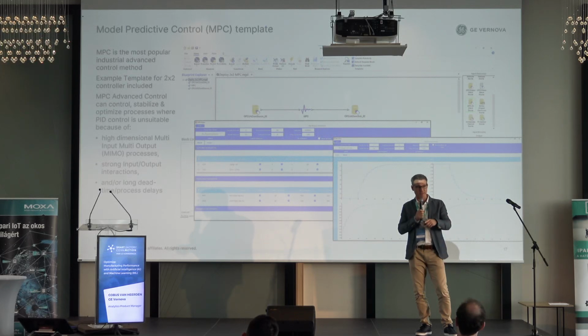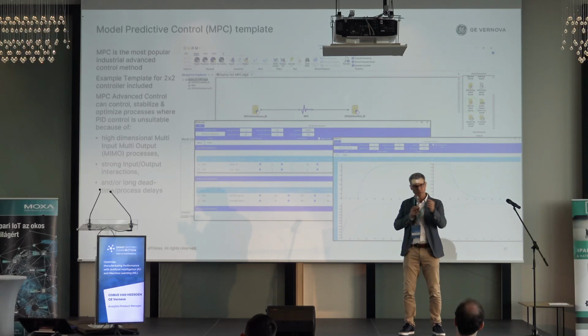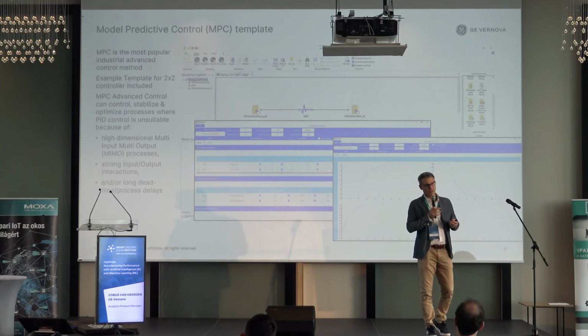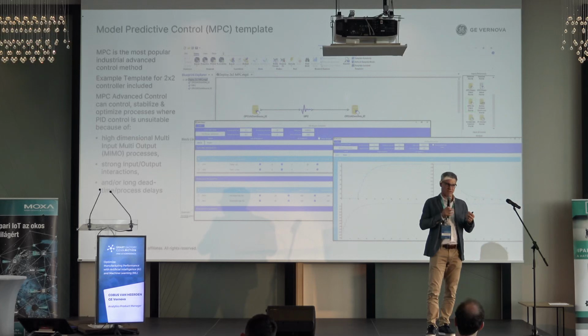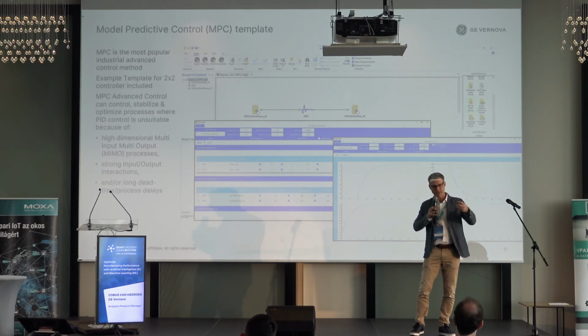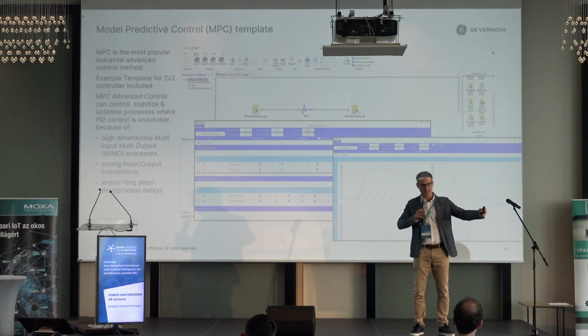PID, proportional integral derivative, is the algorithm controlling 99%, maybe 95%, of all control loops in the world. It's probably in every PLC. We have Moxa, we have Beckhoff, we have many industrial computer suppliers—if you ask them what's inside, often it's PID control loops. That's what's controlling most of it. Now, the thing with PID is one input, one output. It's a linear control technique, and it's not suitable for some use cases, right? Typically when you have multiple things interacting with one another, or long process delays, PID is not necessarily the most suitable.